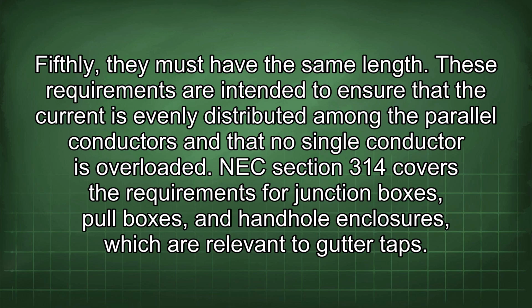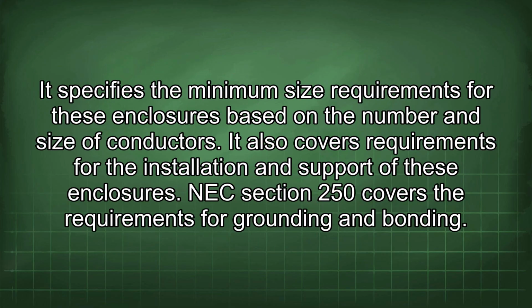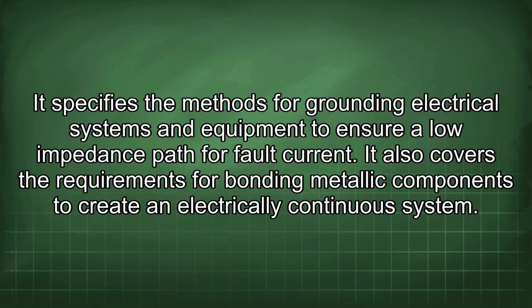NEC Section 314 covers the requirements for junction boxes, pull boxes, and handhole enclosures, which are relevant to gutter taps. It specifies the minimum size requirements for these enclosures based on the number and size of conductors. It also covers requirements for the installation and support of these enclosures. NEC Section 250 covers the requirements for grounding and bonding. It specifies the methods for grounding electrical systems and equipment to ensure a low impedance path for fault current. It also covers the requirements for bonding metallic components to create an electrically continuous system.